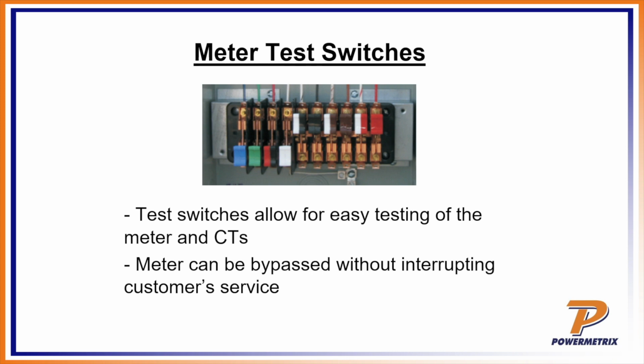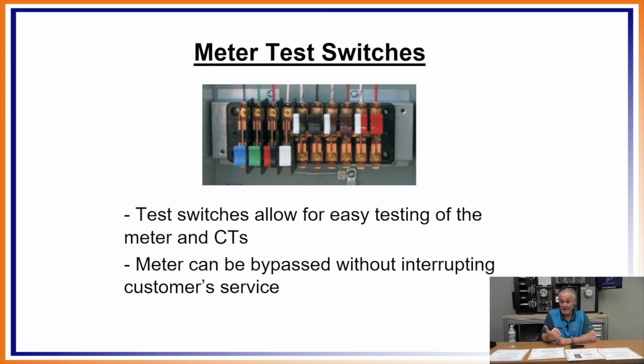Those are going to be your voltages, right? So you can see over here the voltages are on the left side of this test switch. And when I've got those little short stroke switches on there, I know those are going to be my shunts because they don't open fully for my CTs. And then I have the return. So I've got the shunt coming and feeding in from the CTs, and I've got the return going back to them, and that's when I've got that longer stroke blade, but it's got that cross in there where I can insert my duck bill in there, okay?